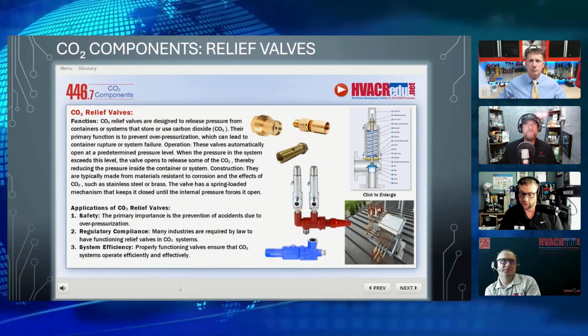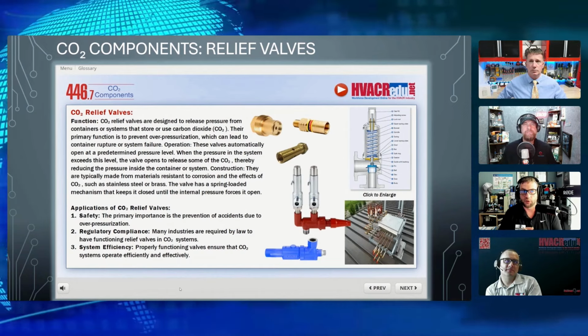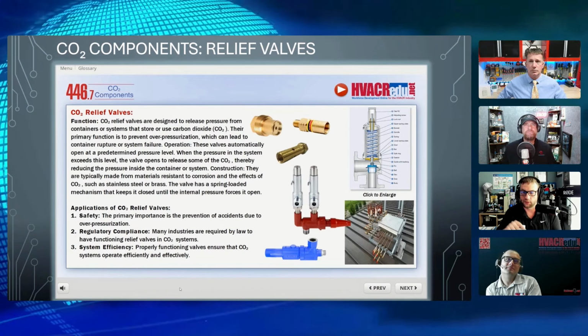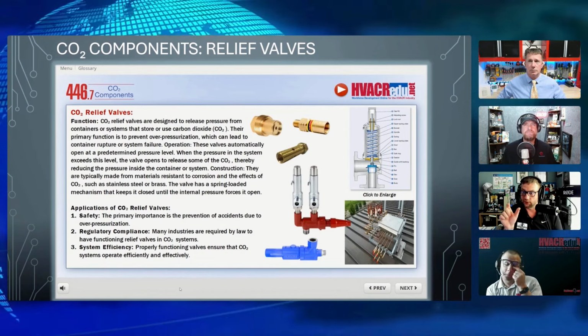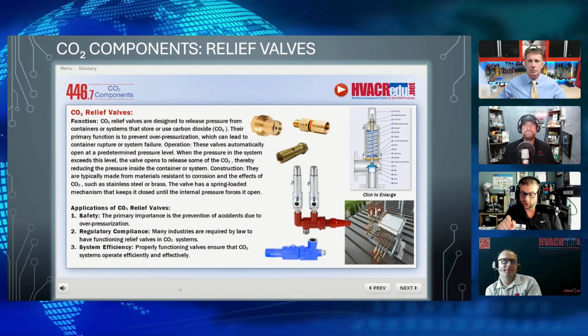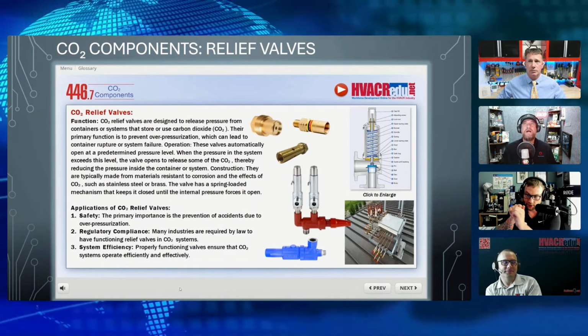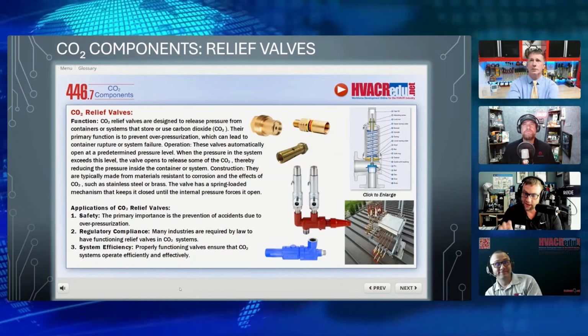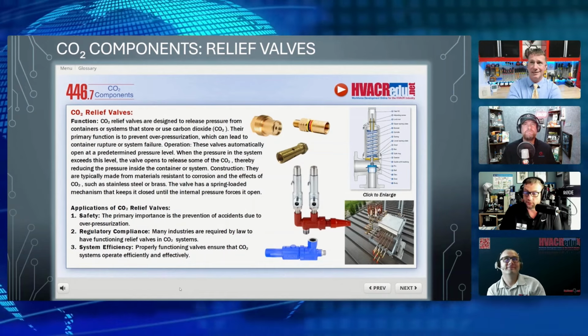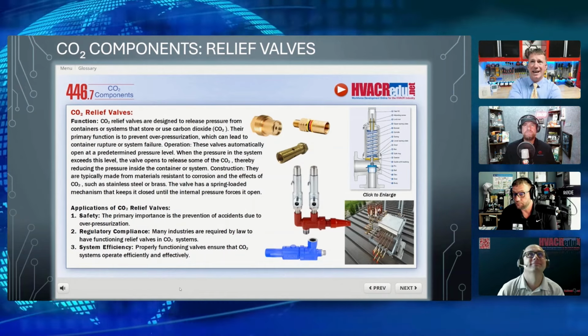It's going to do something horrible to that compressor. That's why in a lot of these transcritical systems, on a regular semi-hermetic, you'll usually see a bolt every inch and a half, 2 inch, right? On a transcritical compressor, it's like every half inch. You can barely get the socket on all the way around to keep that pressure in there. So those ones relief at around 21.8. What's that? Keep those gaskets contained.